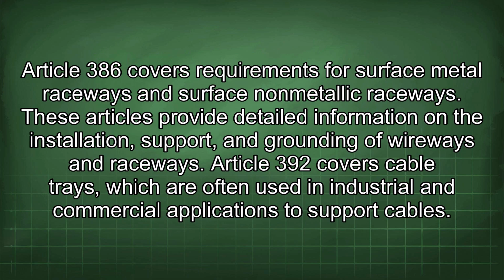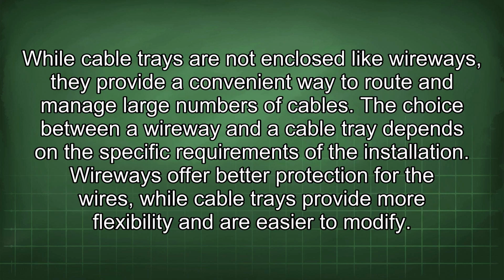Article 386 covers requirements for surface metal raceways and surface non-metallic raceways. These articles provide detailed information on the installation, support, and grounding of wireways and raceways. Article 392 covers cable trays, which are often used in industrial and commercial applications to support cables. While cable trays are not enclosed like wireways, they provide a convenient way to route and manage large numbers of cables. The choice between a wireway and a cable tray depends on the specific requirements of the installation. Wireways offer better protection for the wires, while cable trays provide more flexibility and are easier to modify.